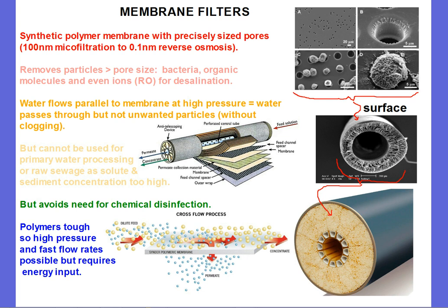And that means because these pores are so small, it can remove bacteria, organic molecules, and even ions in reverse osmosis in desalination. Now you have water flowing parallel to the membrane at high pressure, which means the water passes through, but the particles do not, and it doesn't cause the particles to clog the pores because the particles are moving parallel to the pores rather than pushing into the pores.